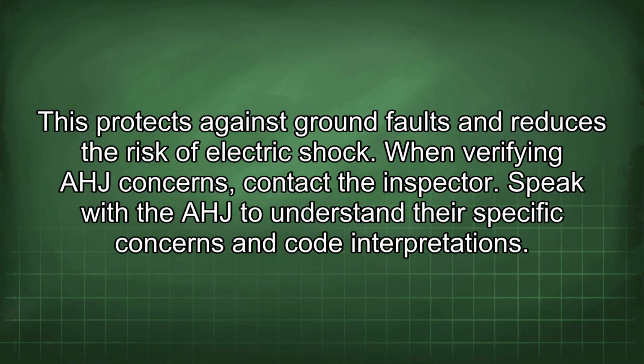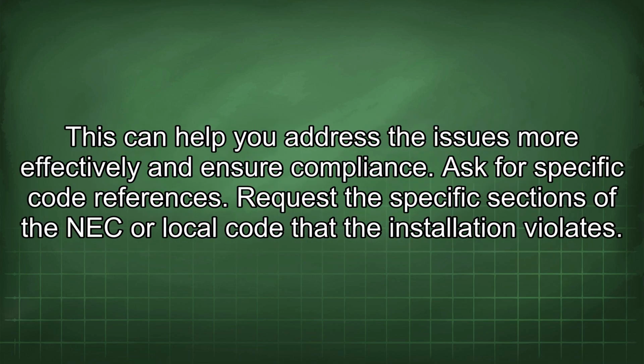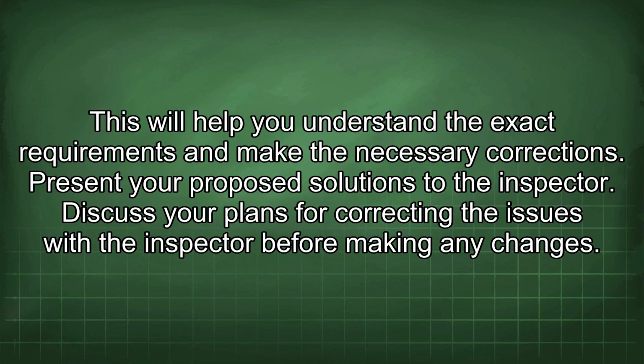When verifying AHJ concerns, contact the inspector. Speak with the AHJ to understand their specific concerns and code interpretations. This can help you address the issues more effectively and ensure compliance. Ask for specific code references. Request the specific sections of the NEC or local code that the installation violates. This will help you understand the exact requirements and make the necessary corrections.